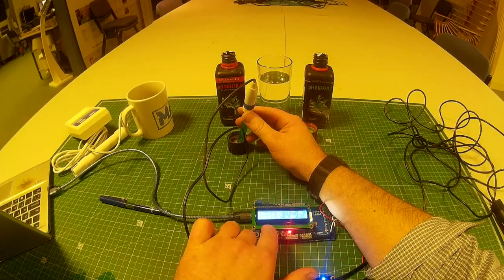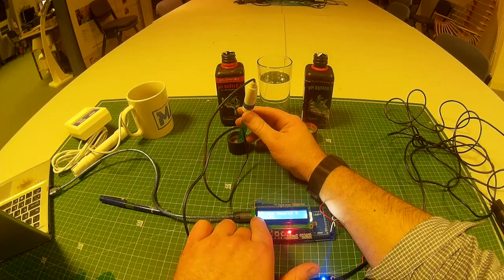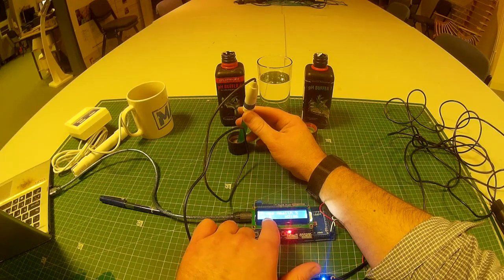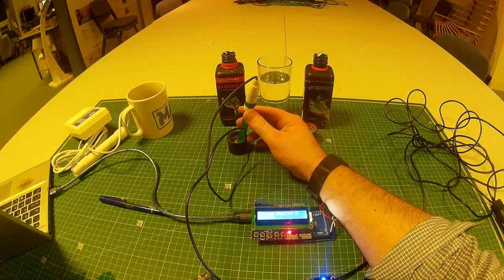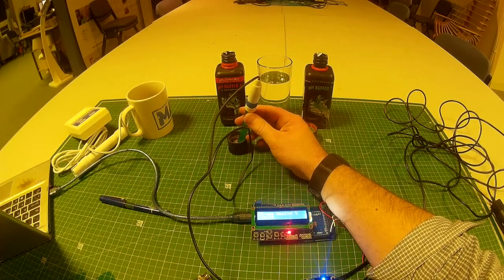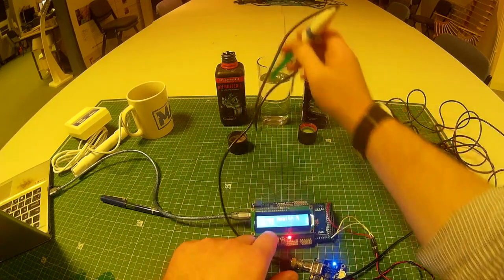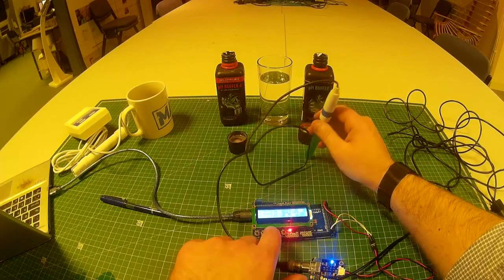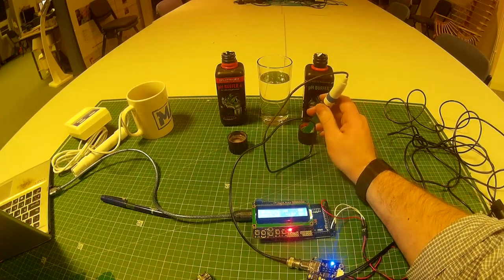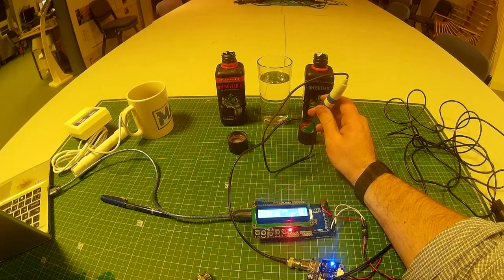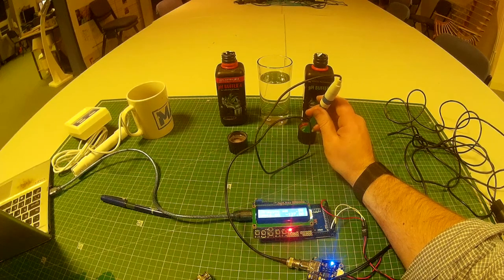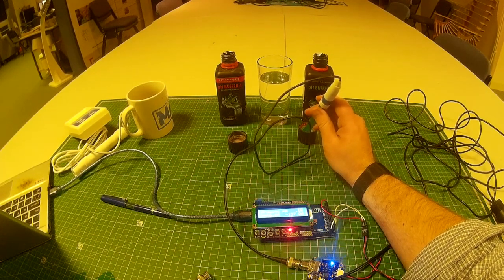So let's have a look at its health. Its health 1 is 0, its health 2 is 86 and its health 3 is 74. So this probe's actually failed by its first health factor. It still reads pH quite well. Like if we put it back in the 7, it will slowly go back up to 7.